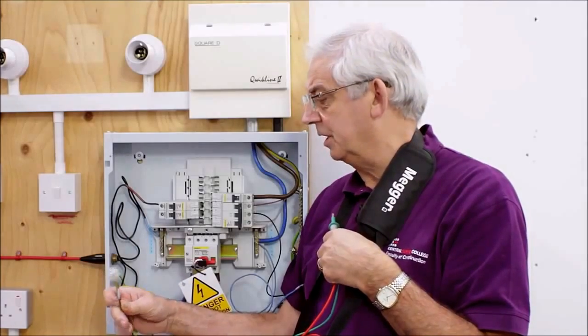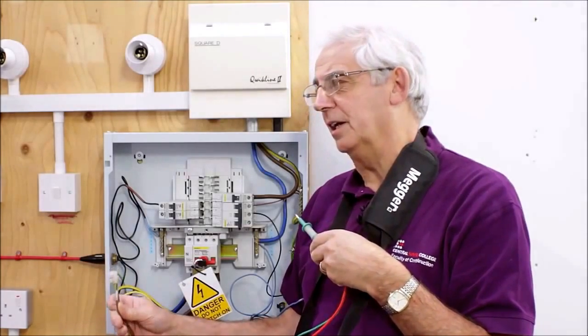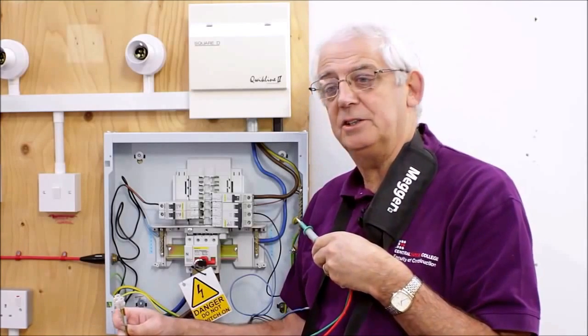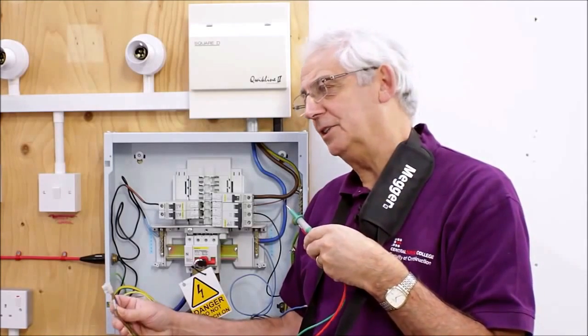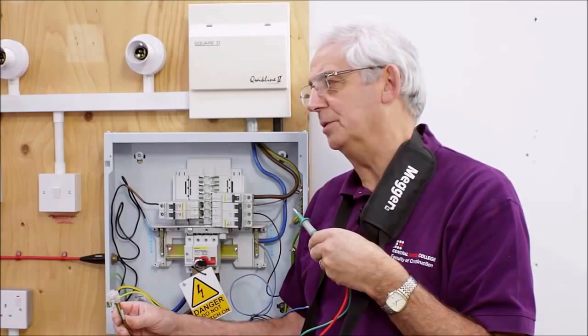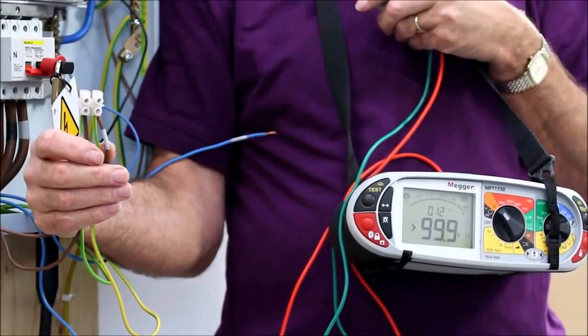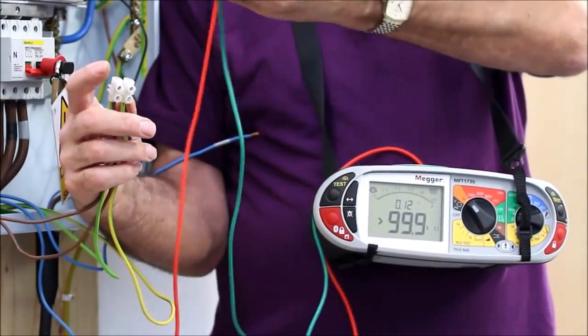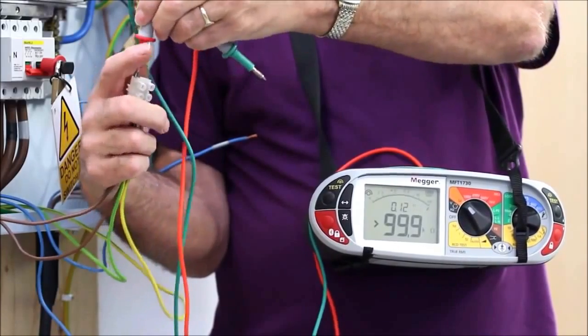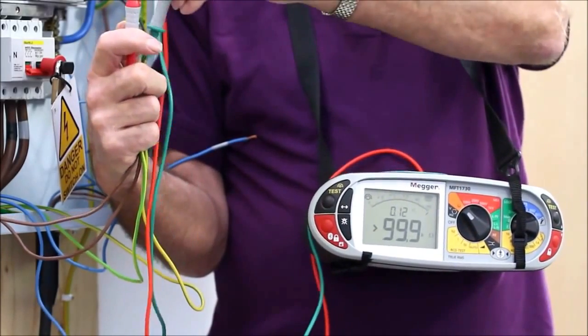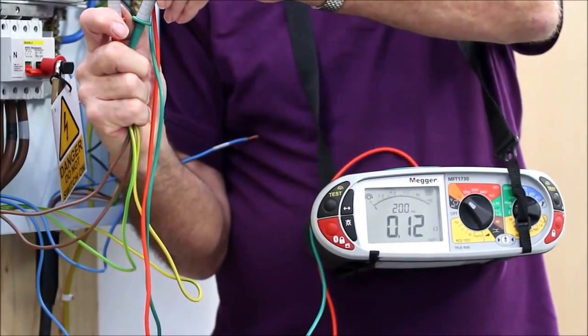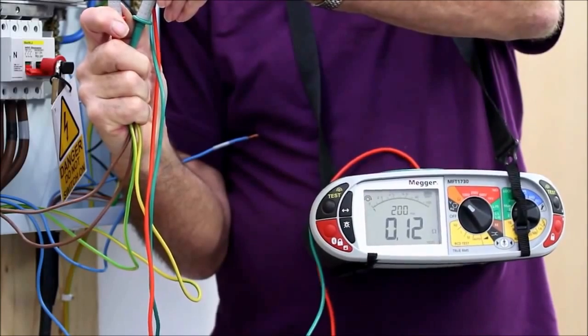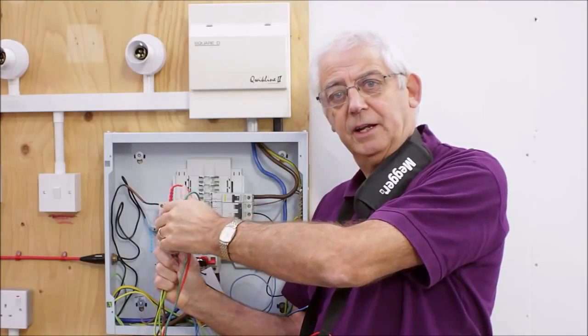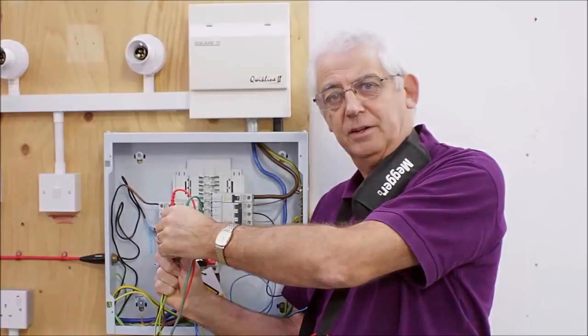What I'm going to do now is take a measurement here to give me an indication of the value which I should get at each socket outlet. In reality, it should be half of one of the original measurements, so 0.11, 0.12 would be what I'm expecting to get. Okay, that tells me what I should get now at each socket between line and earth.